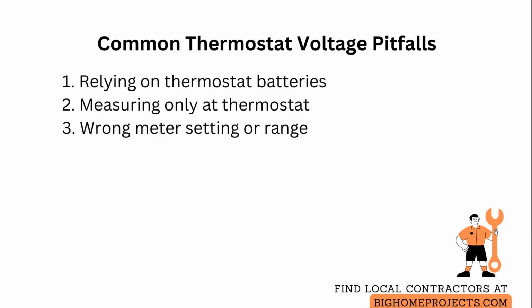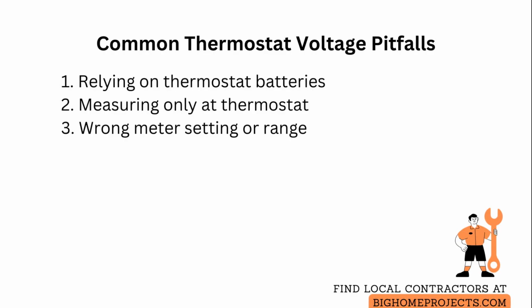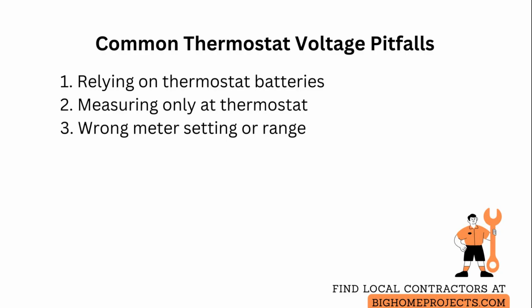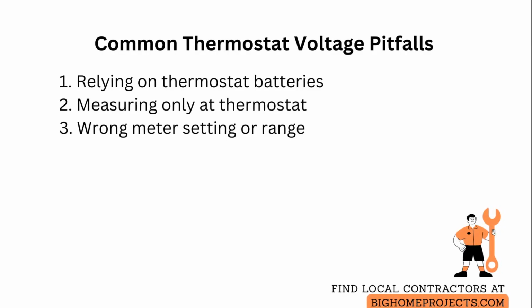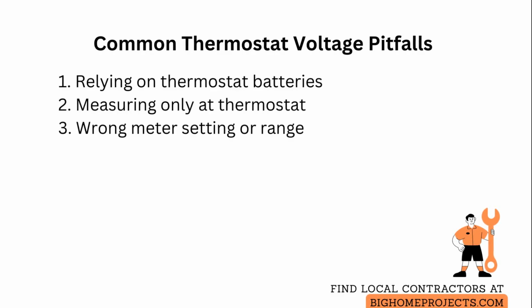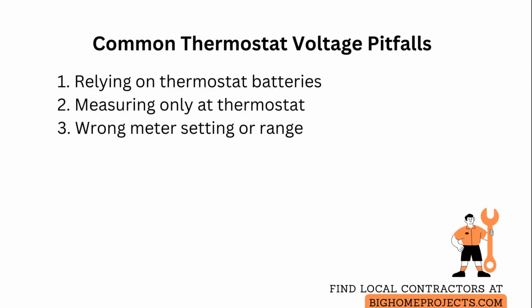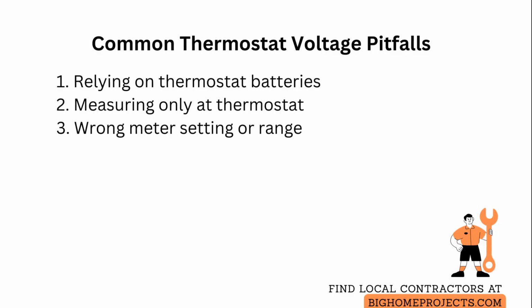Another frequent issue is reading only at the thermostat and not at the control board, where a loose connection or splice inside the wall can drop voltage. Measure at both ends and trace continuity if readings differ. A third problem is using a meter set to the wrong range or to direct current, which gives false readings. So set the multimeter to the alternating current voltage range, appropriate for low voltage systems, and confirm meter calibration or test on a known source first.